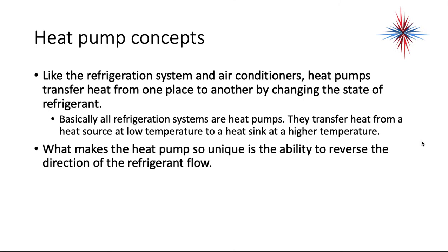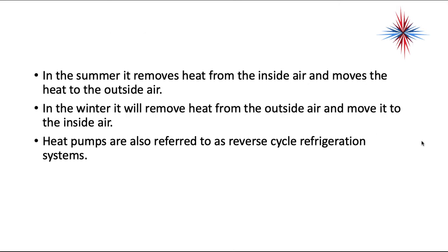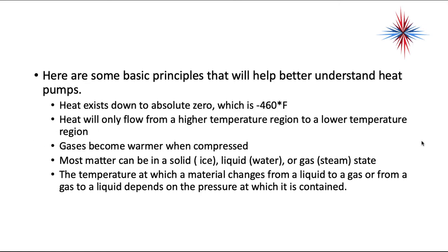Like refrigeration and air conditioning systems, heat pumps transfer heat from one place to another by changing the state of a refrigerant. Basically, all refrigeration systems are heat pumps. They transfer heat from a heat source at a low temperature to a heat sink at a higher temperature. What makes the heat pump so unique is the ability to reverse the direction of this refrigerant flow. In the summer, it removes heat from the inside air and moves the heat to the outside air. In the winter, it will remove heat from the outside air and move it to the inside air. Heat pumps are also referred to as reverse cycle refrigeration systems.